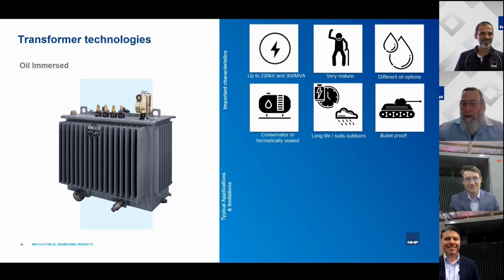And eventually this transformer cooked itself and got to a stage where the paint was peeling off the outside of the tank. I remember an article in the local paper where a school kid had burnt his hand on it. It had got that hot. I remember opening up this transformer and looking inside, and there was just black sludge inside the transformer. In actual fact, it had got down below the top of the windings, and even to this day, I am absolutely amazed that transformer had not arced.